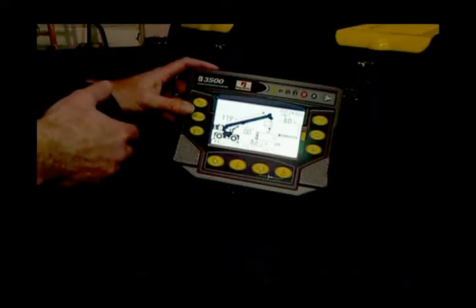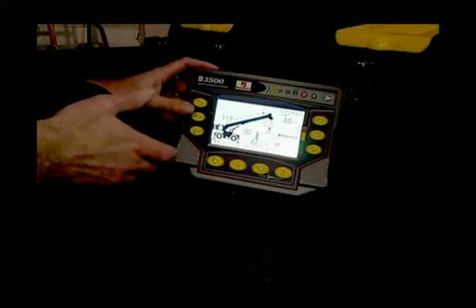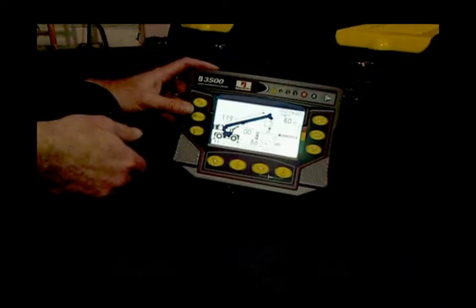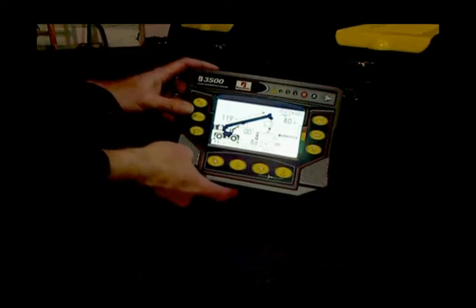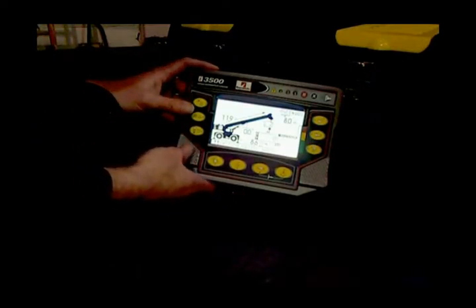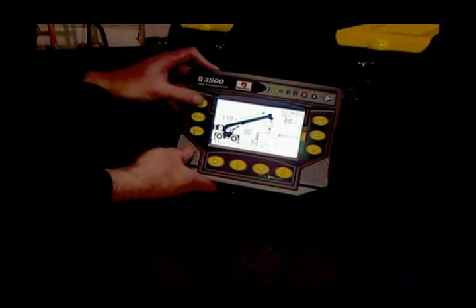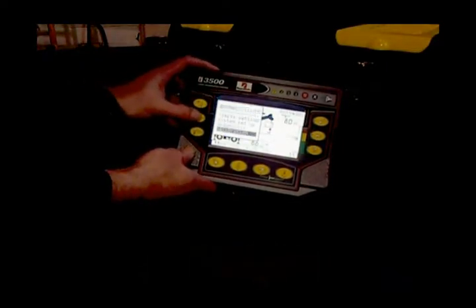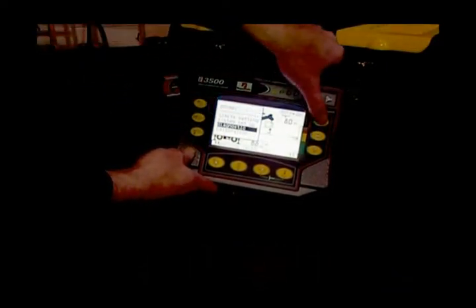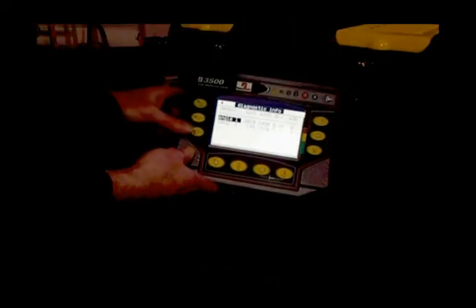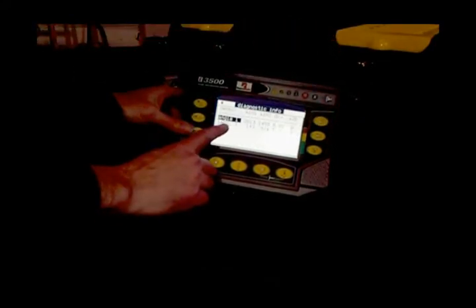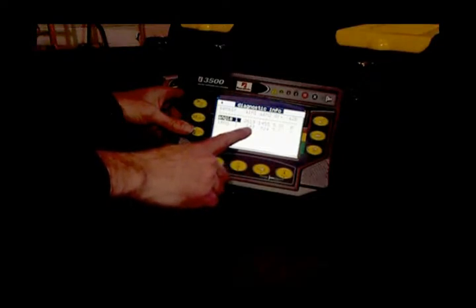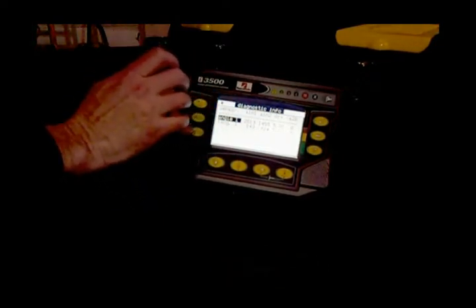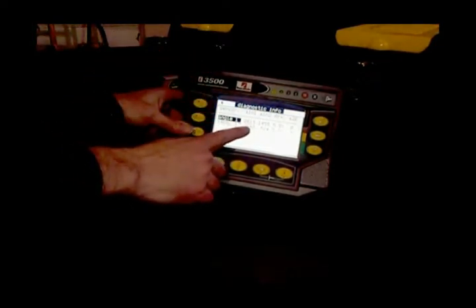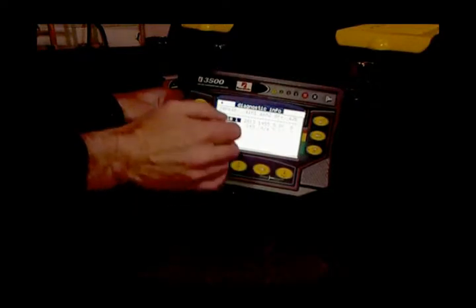So let's say we've already replaced our length sensor, which is the potentiometer, or we've replaced the circuit board. What we're going to want to do is begin the calibration process. So we're going to come in and go to Diagnostics and hit the check mark. What we're going to see here is length 1. And what I want for length 1, when it's fully retracted, is a digital value under AIN1 of 100.